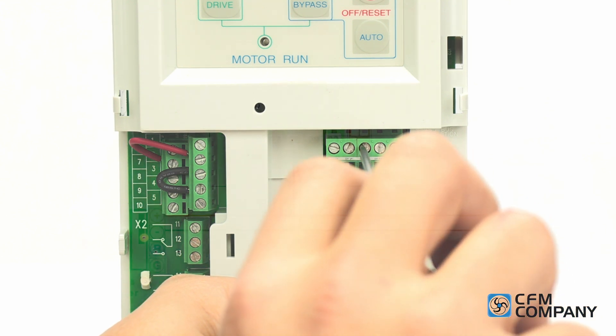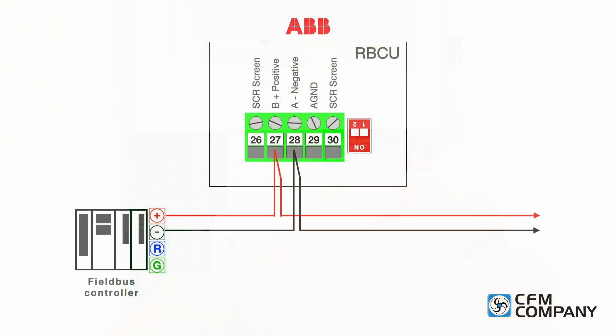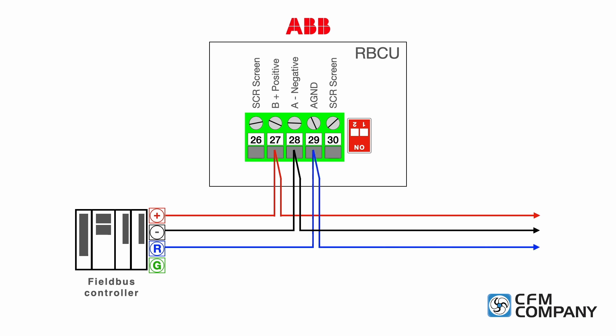Connect the negative network wire to terminal 28. In our example, this is the black wire. For three wire communication networks, connect the optional reference wire to terminal 29. Note that the network wire shield is not landed to the bypass control unit.